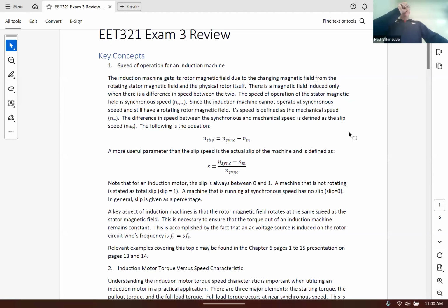Now, that doesn't mean synchronous speed doesn't exist. It still exists. So remember, there are two magnetic fields, one on the rotor, one on the stator. The stator magnetic field, usually that's where the current comes in to drive an induction motor. That's going to be 60 hertz, and that's going to create a magnetic field that rotates at synchronous speed. And we can find that by doing our right-hand rule, taking our fingers and pointing. We've done that extensively. That's the magnetic field that we're talking about on the stator.